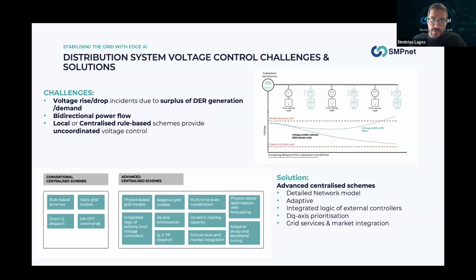It has to integrate any local controls available. So if there is an OLTC there, its control has to be integrated in the advanced solution. In that way, the dispatch that will be calculated for the DERs will not battle the local controller and will coordinate with it to provide the optimal solution to resolve the voltage issues. Then there is DQ axis prioritization, that means that we can use either active or reactive power to solve voltage issues. And through an advanced centralized scheme, we can have the respective costs for every solution, and in that way it is prioritized properly what should be used to resolve the issue. And of course, through an advanced centralized scheme, you can also have grid services like the TSO-DSO coordination scheme that we saw previously, as well as integration with local energy markets.